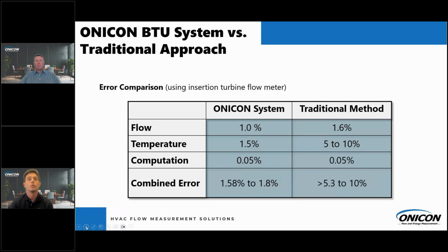So when you compare the full error across the board between the ONICON BTU system, such as the System 1000, versus the traditional approach, you can see the combined error of 1.58 to 1.8% compared to the traditional amount of 5.3% up to 10% error. Now, as I mentioned earlier, that's in a perfect delta T of a 10 degree differential. That error is going to start approaching way closer to 20% if you have a lower delta T.